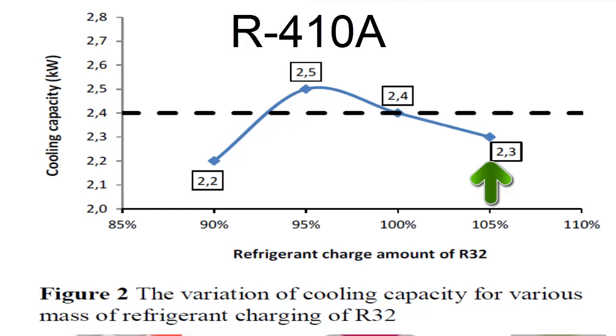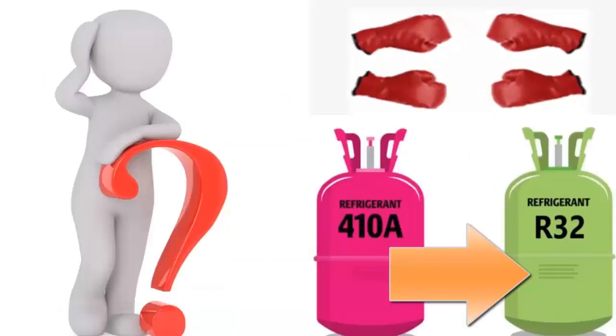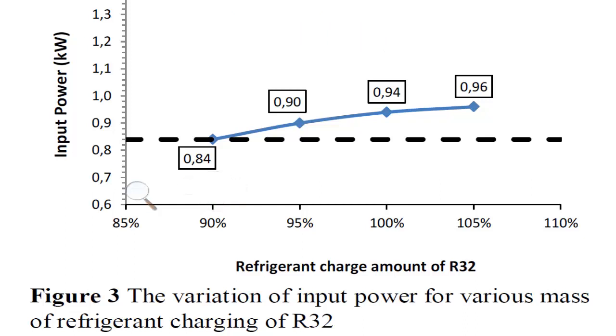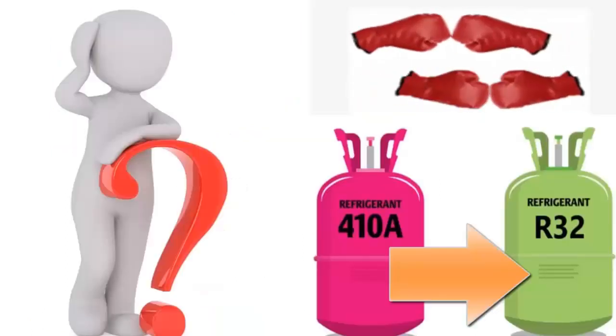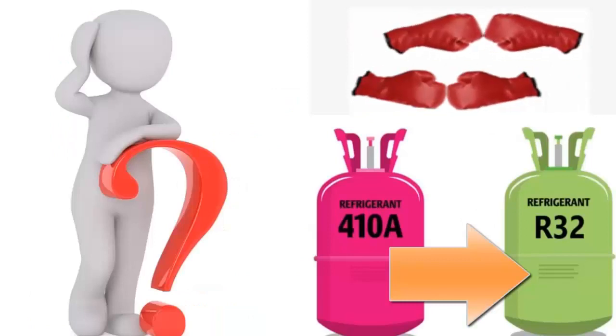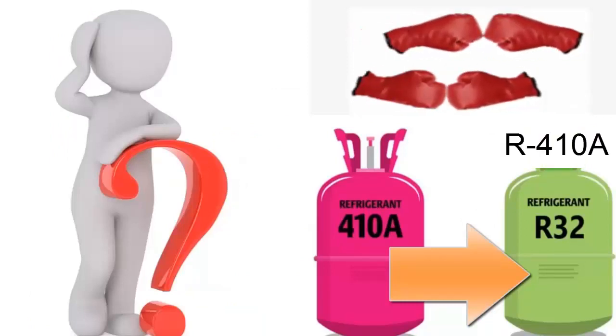7. Charging with 90% of the original R-410A amount using R-32 will maintain similar electrical consumption, but with lower cooling capacity. 8. Beyond 90%, the compressor's electrical consumption will increase compared to what it used to be with R-410A.